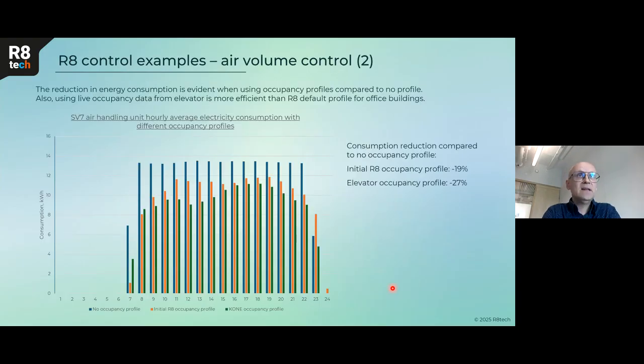And about the results, this is one case study we did. The blue shows the calculated fan consumption while the building is using full speed, and before and after the regular occupied time we're working at half speed, 1 hour before and 1 hour after. While we added our initial occupancy profile, the orange, we got 20% electricity fan savings, and when we had live data from elevators, we got in total 27% savings for the ventilation fans. And in addition, heating and cooling coils as well, depending on the season.